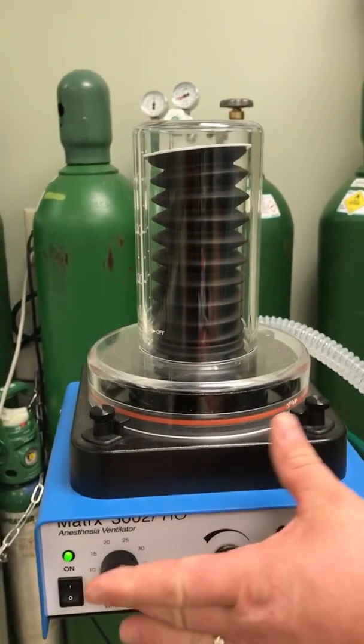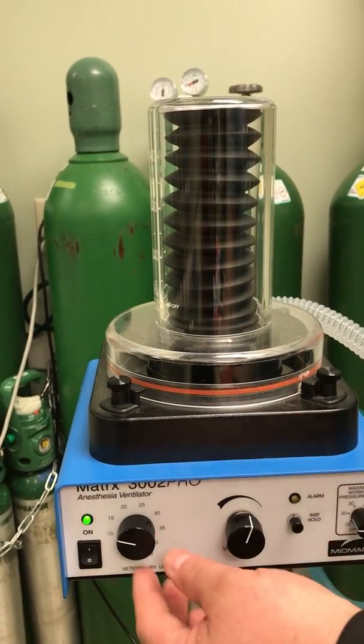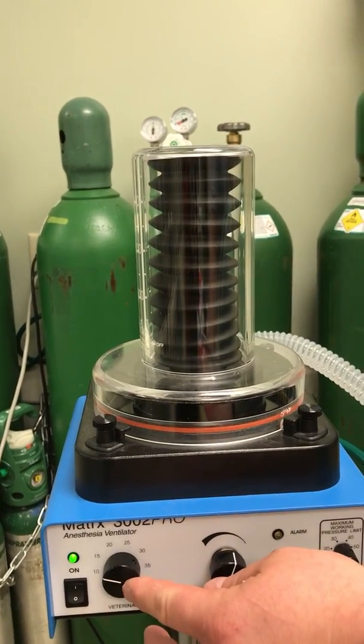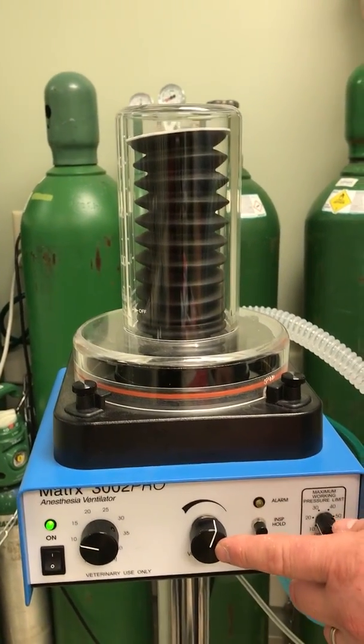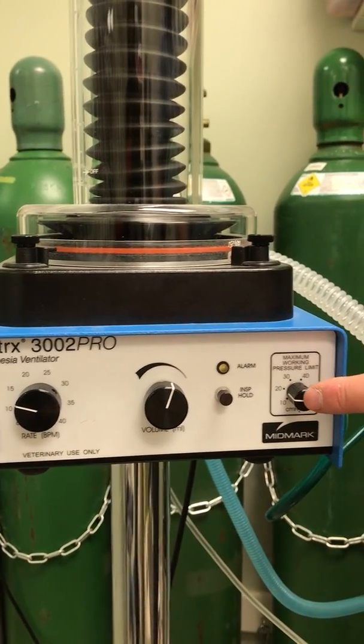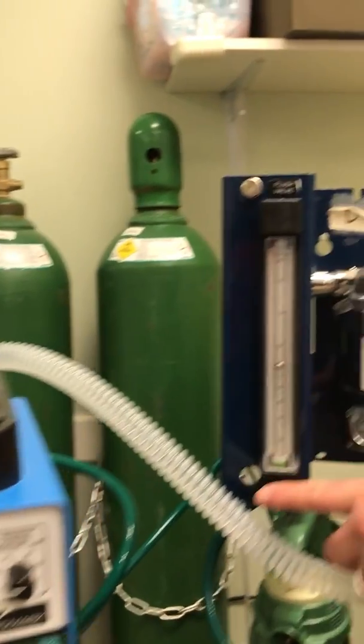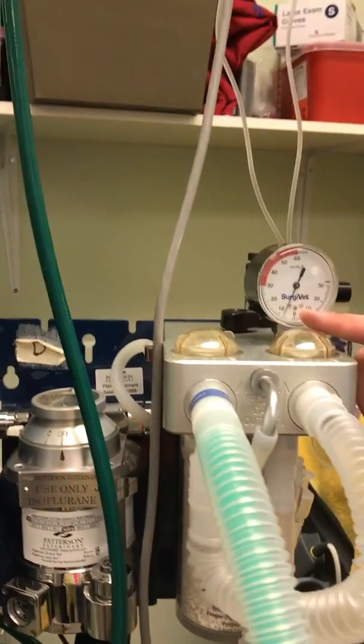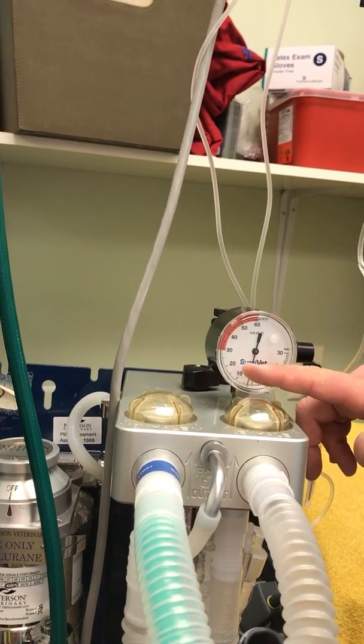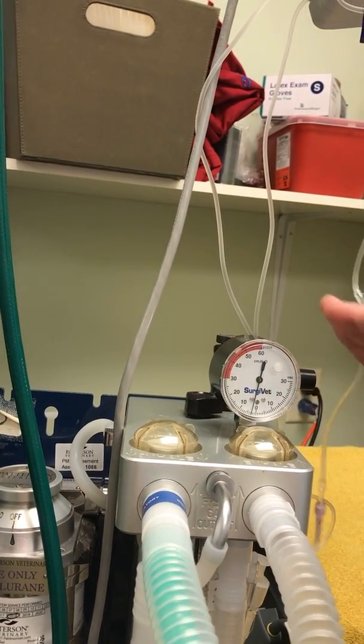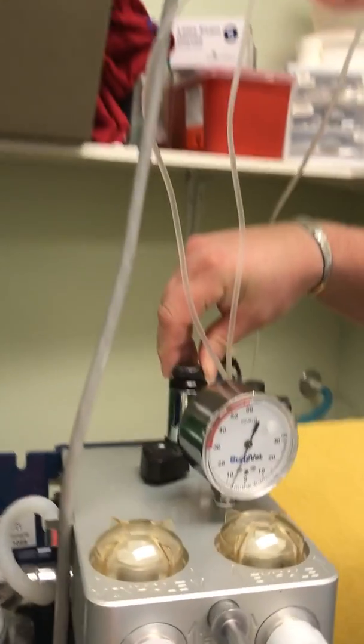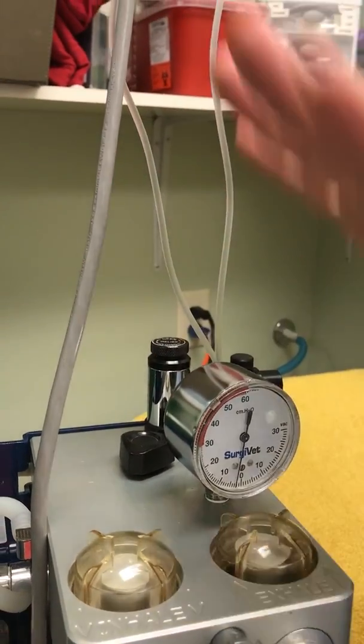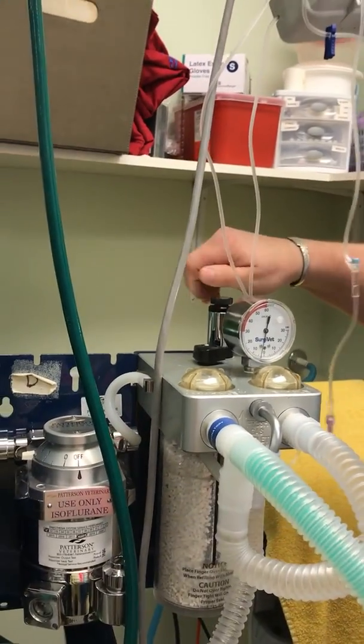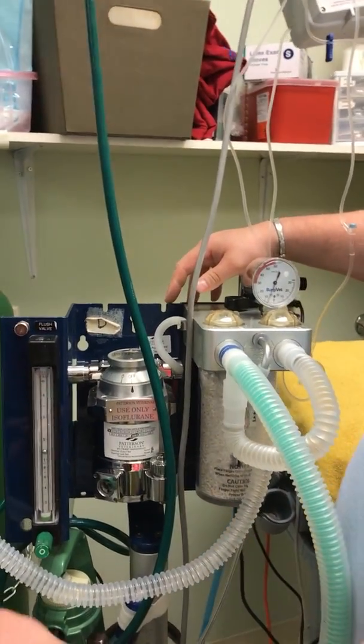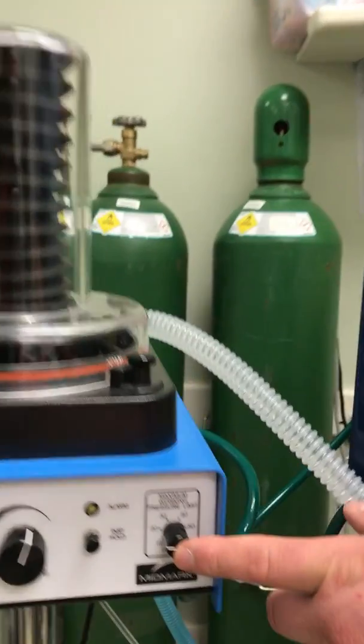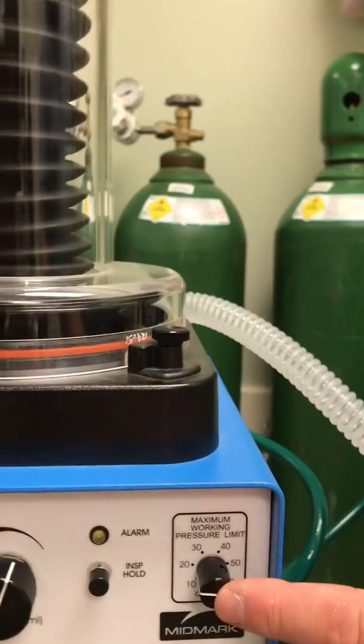So at this point you have the number of breaths per minute set. So this is our breathing rate. We have our flow set. We have our max alarm set. And we have oxygen on. And we're making sure that our pressure gauge does not go above 20 on this especially. And we want to keep it closer to 10 to 15. And we have to make sure that our pop-off is off, or else this whole system will not retain any pressure. So when we hit a pressure above 20, there will be an alarm sounding, but we need to realize...